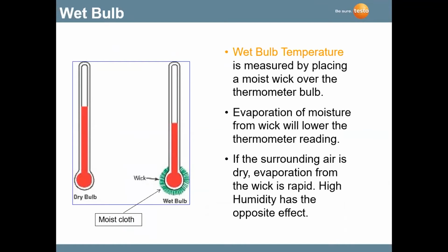So if we get into wet bulb, most of you are familiar with the term wet bulb. In the past, we used a wet bulb, which is a thermometer with a wick on it. And we used to moisten that wick with distilled water. We'd do a comparison of a dry bulb and a wet bulb by spinning what they call a sling psychrometer. And the difference between the wet bulb reading and the dry bulb reading would provide us the relative humidity.